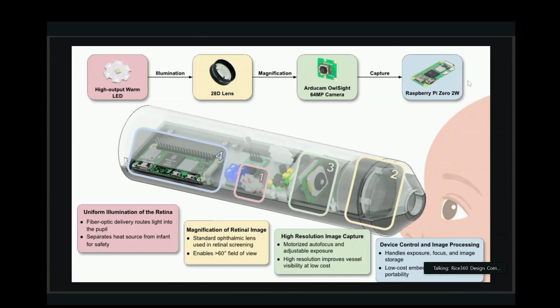Now, what's happening underneath the device? First up, we illuminate the eye using a high output LED, which gives us sufficient light to reach the back of the eye. To ensure safety, we basically separate the hazardous heat from the infant's eye using fiber optic cables, which route the light from the back of the device to the tip of the device. Next, the reflected light is magnified using a standard 28D ophthalmic lens, which gives us around a 70-degree field of view, which is enough to see the peripheral retina where early cases of ROP develop.